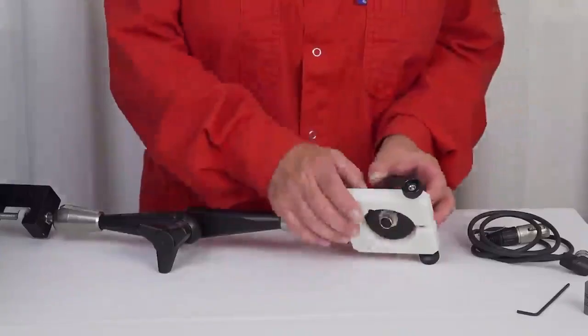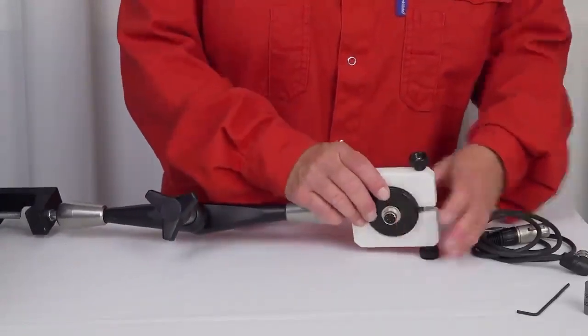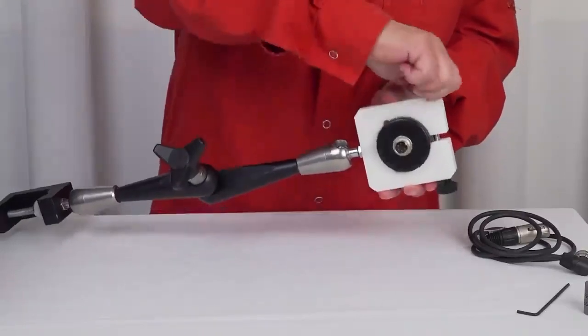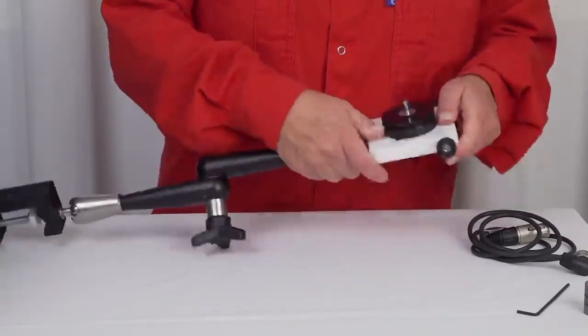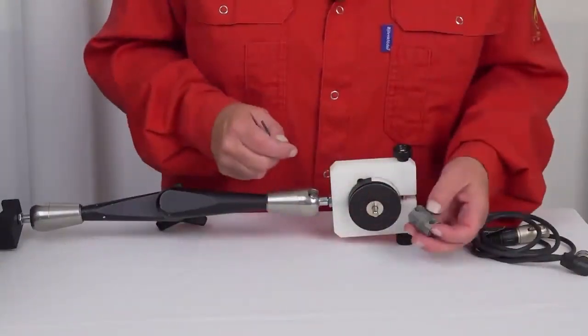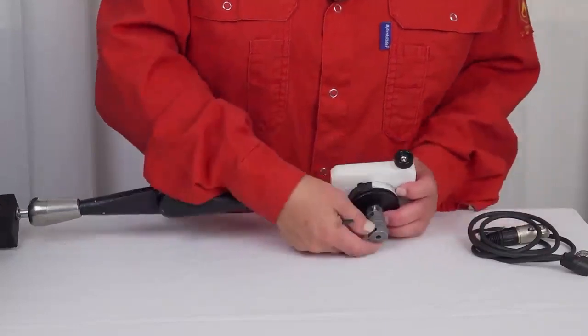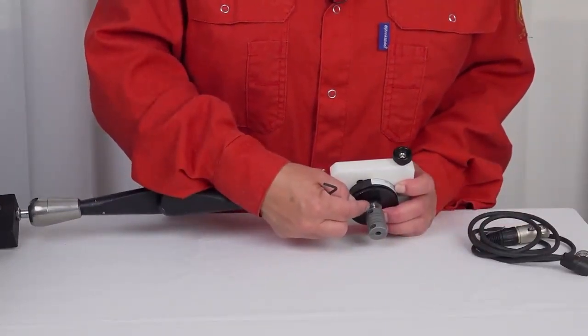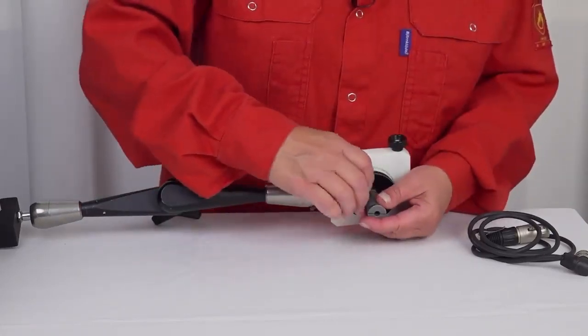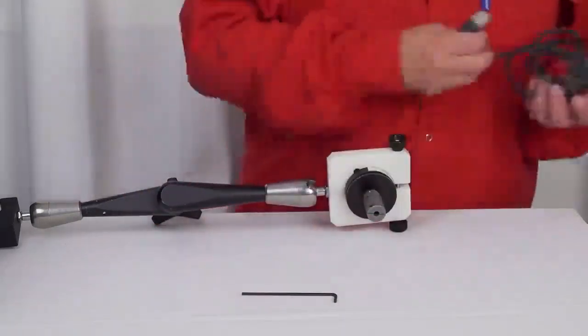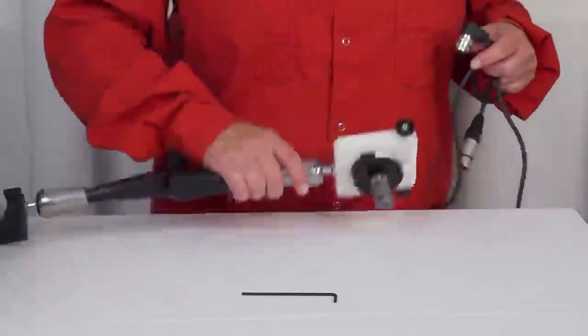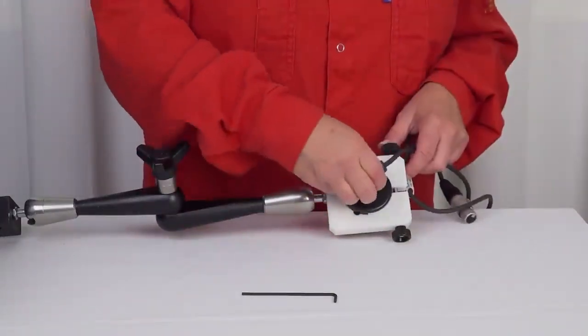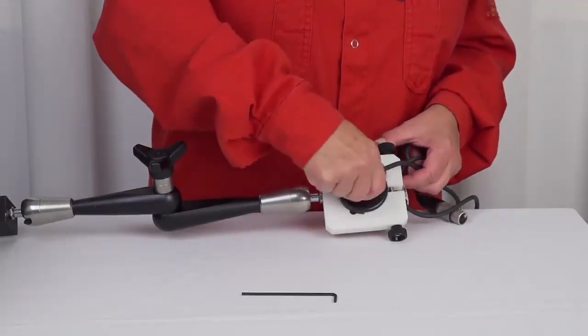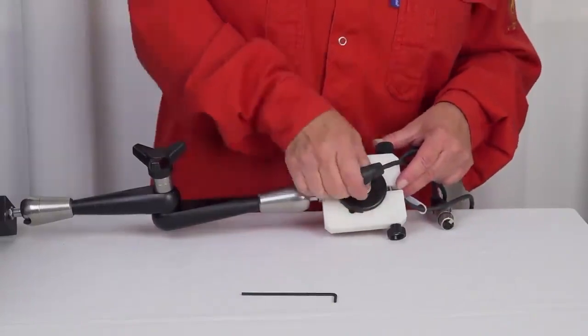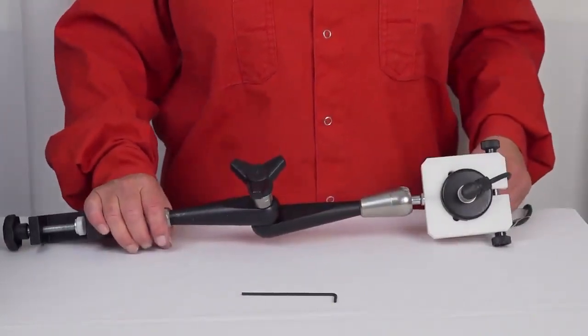I go over to mounting the transducer in the white holder. And the flex coupler at the axis. This must have a distance in between here. And the cable is connected on the other side. And now we're ready to mount it on the circuit breaker.